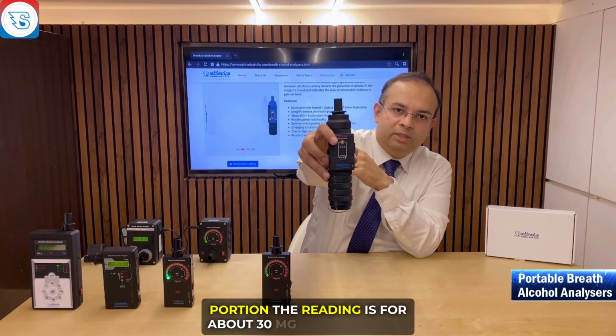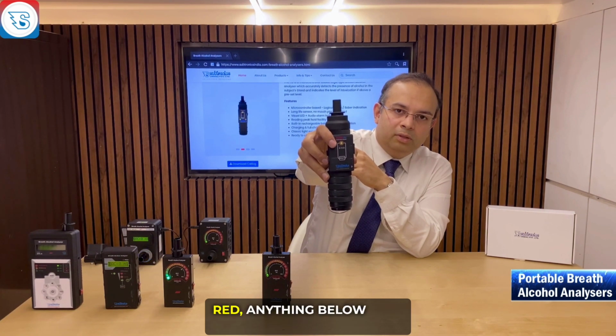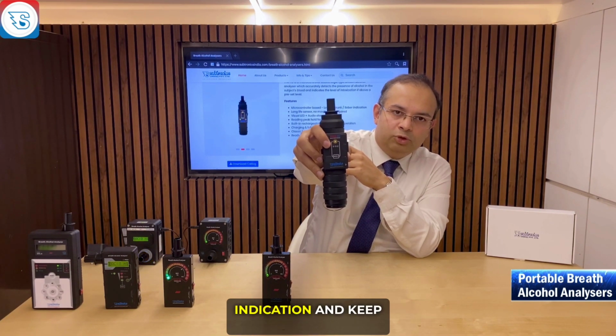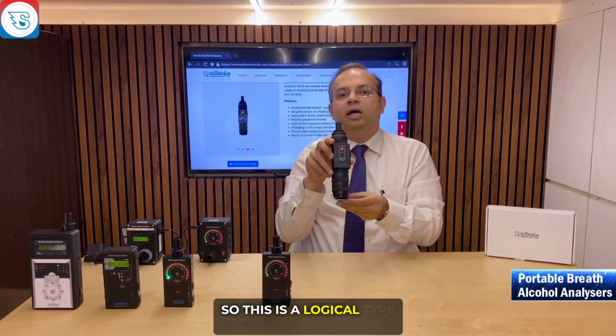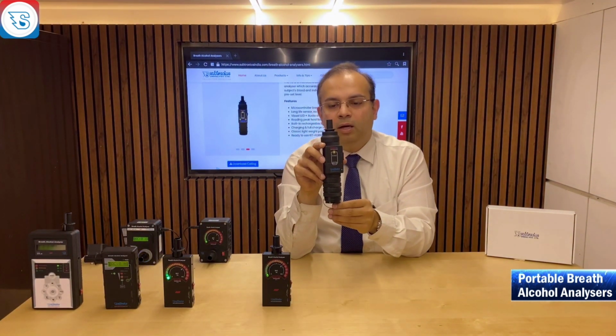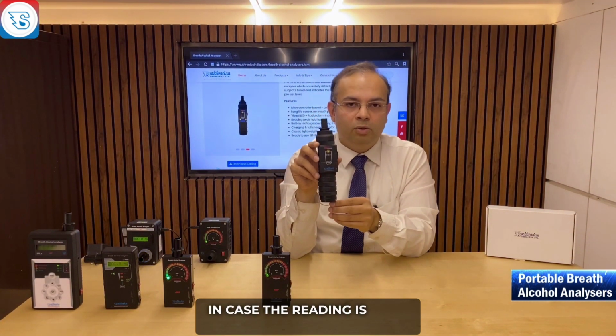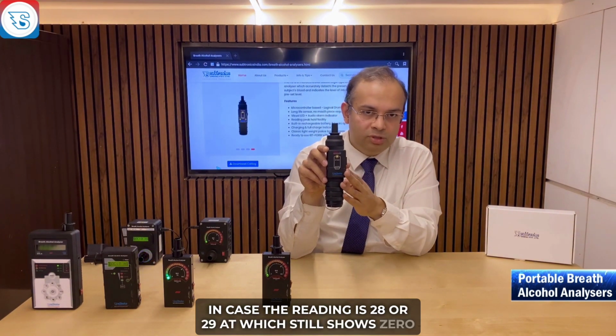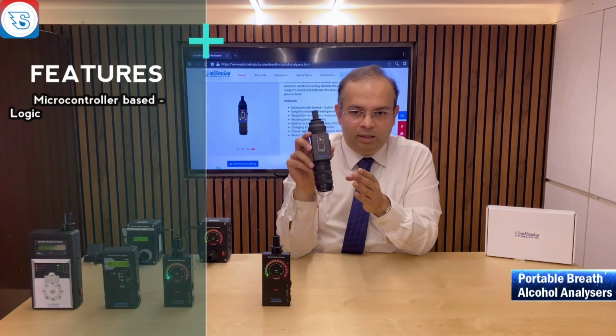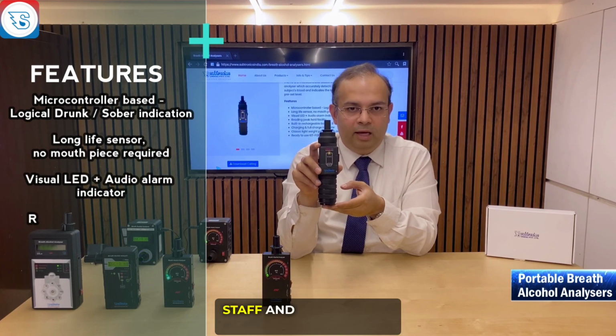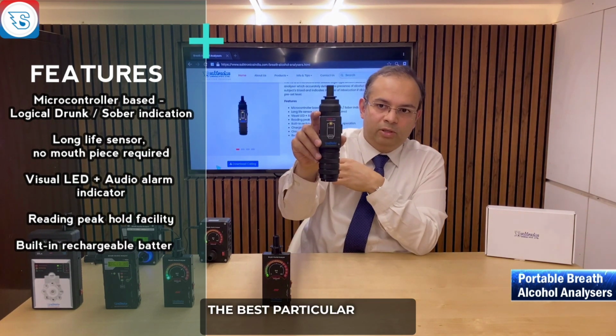Once you ask the person to exhale on the sensing portion, a reading above 30 mg will show you red. Anything below that will not show any indication, and it will keep showing green. So this is a logical type device that we suggest. In case the reading is 28 or 29, it will still show 0. But anything above 30, it's very clear. For plants who need to check their staff and need a logical decision, this is the best choice.